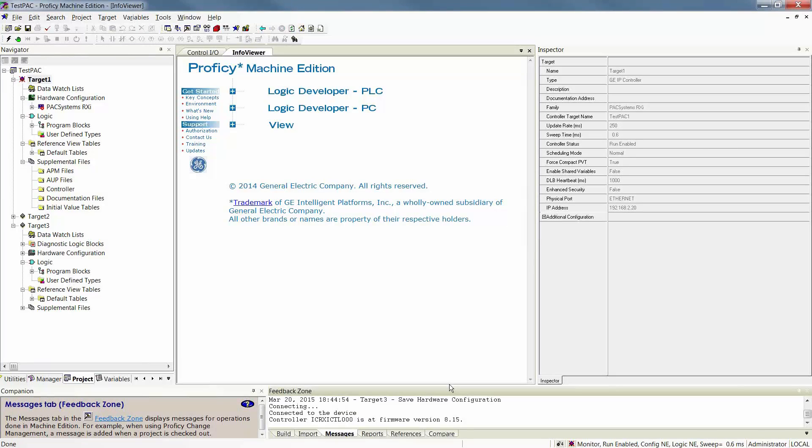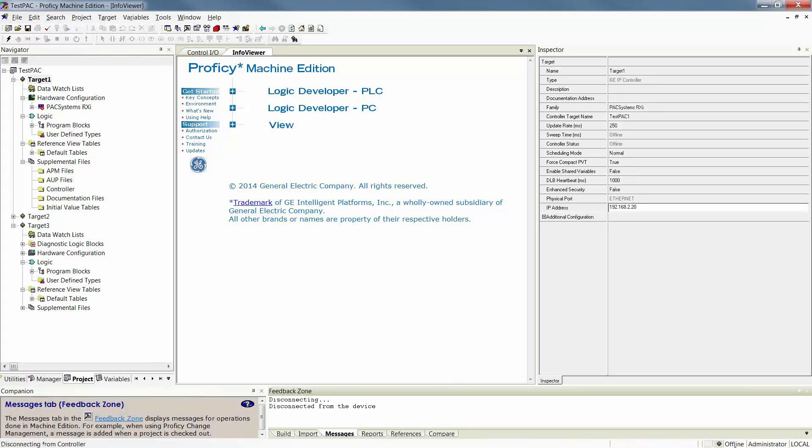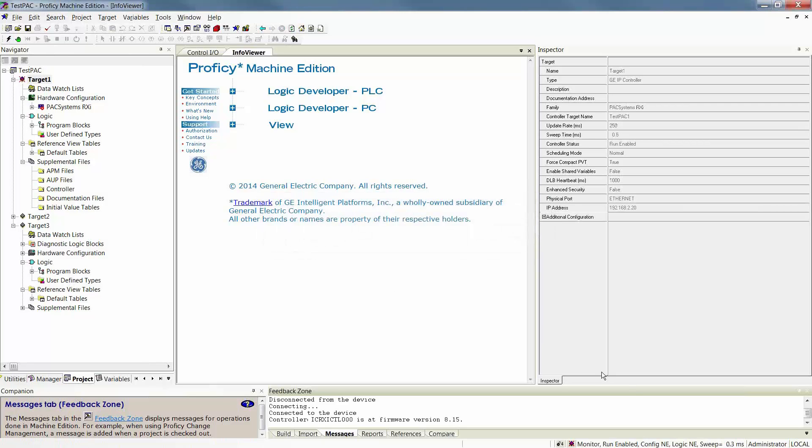I've now gone online. You'll know that you're online because your indication in the lower right-hand corner of Machine Edition references and shows offline whenever you're offline. You also see a gray symbol next to your target. When I go online, you will by default go online in Monitor Mode. This is the safe mode. This mode allows you to view, monitor, and watch your data watch list without changing anything.